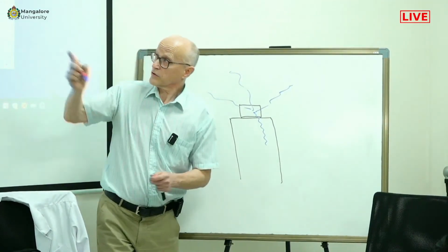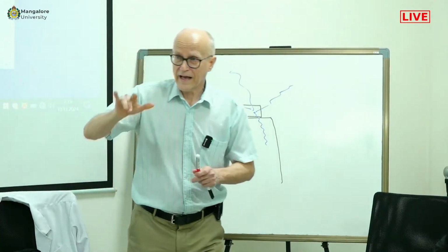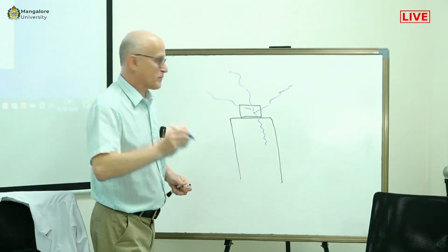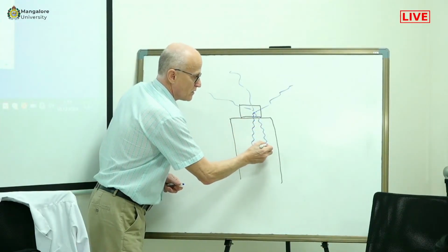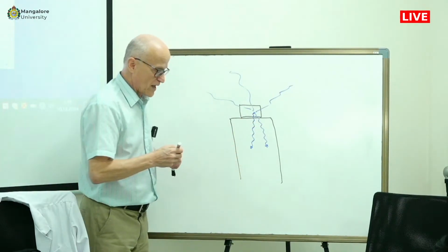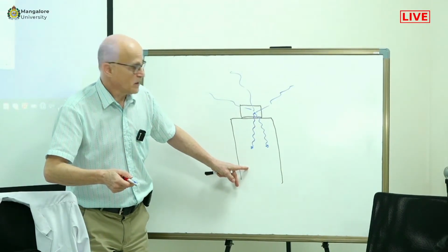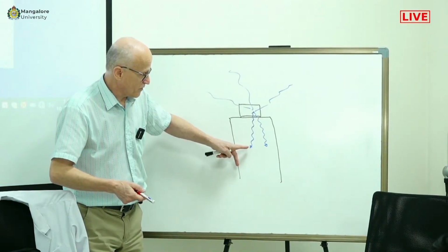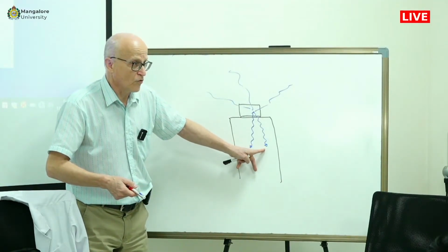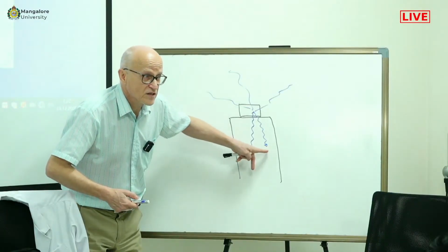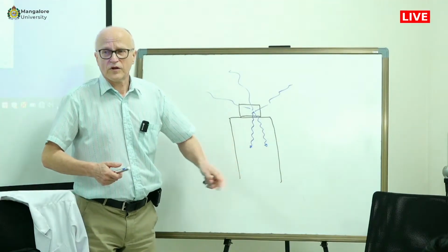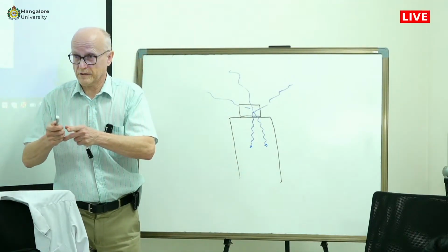But what's the coincidence effect? It's this one, because this cobalt-60 emitted 2 photons at more or less the same time. It may happen that both photons are coming here. So what happens in the MCA, in the multi-channel analyzer? It doesn't detect the energy of this photon only or this photon only. It detects the sum of these energies. So this is called true coincidence.